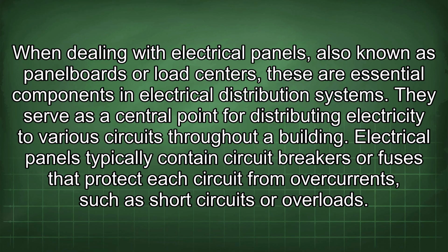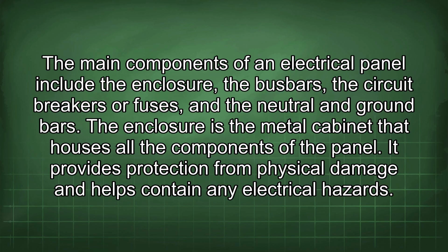When dealing with electrical panels, also known as panel boards or load centers, these are essential components in electrical distribution systems. They serve as a central point for distributing electricity to various circuits throughout a building. Electrical panels typically contain circuit breakers or fuses that protect each circuit from overcurrents, such as short circuits or overloads. The main components of an electrical panel include the enclosure, the bus bars, the circuit breakers or fuses, and the neutral and ground bars. The enclosure is the metal cabinet that houses all the components of the panel.